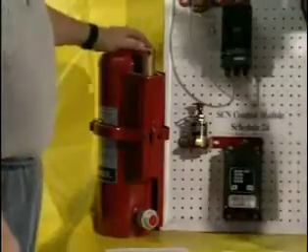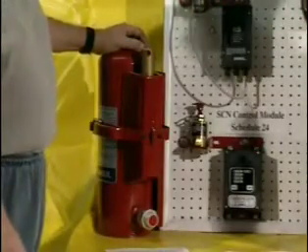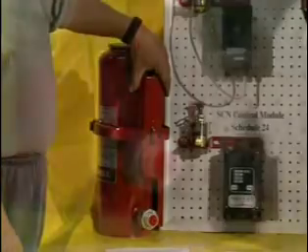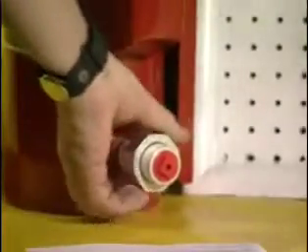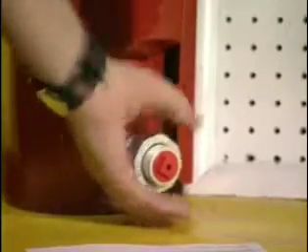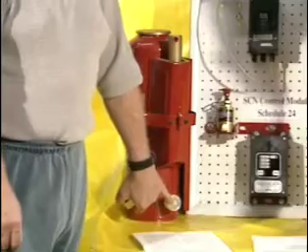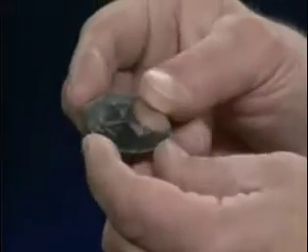Over here, Don, we have an Ansul 20-pound pneumatic. The pneumatic means that the cartridge is mounted right on the tank itself. This bush and disc union on the tank should be hand tight, snug only. You notice on the inside you've got your bursting disc. This is what holds the chemical in until the system's ready to fire.